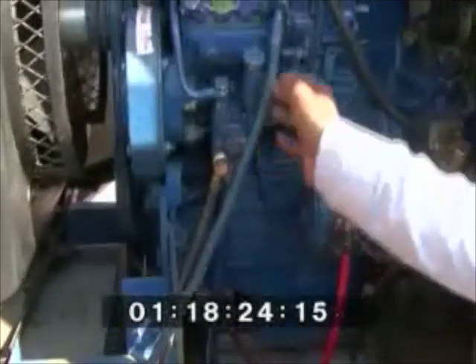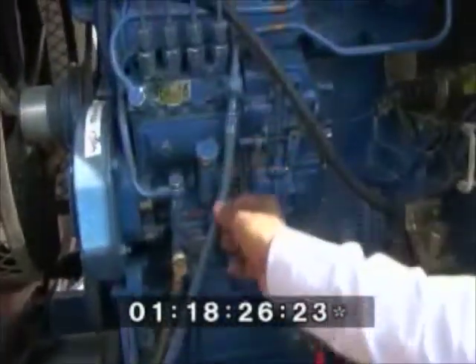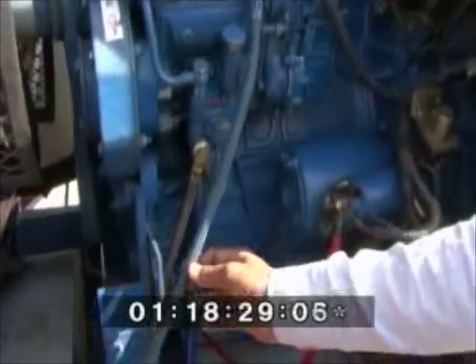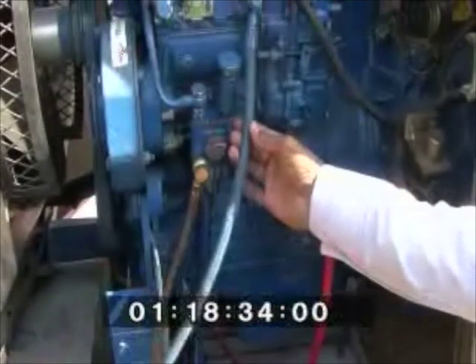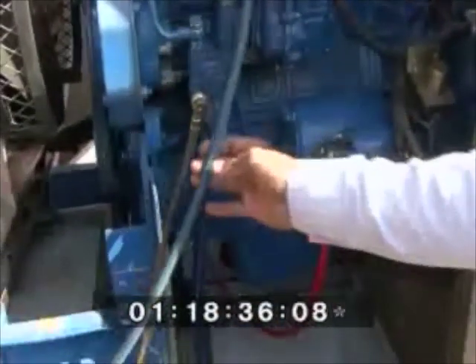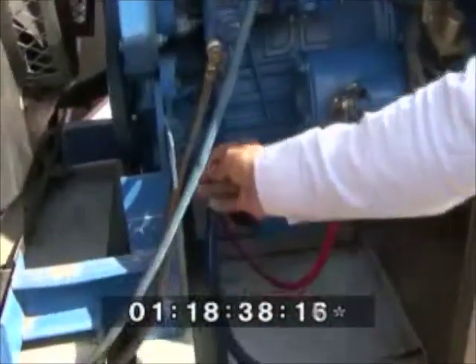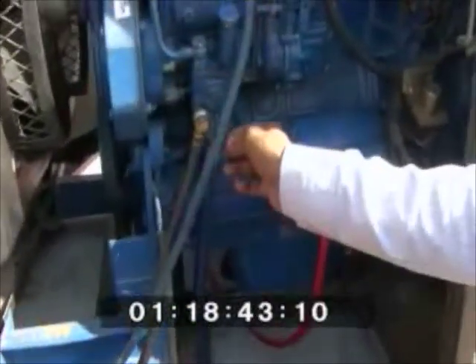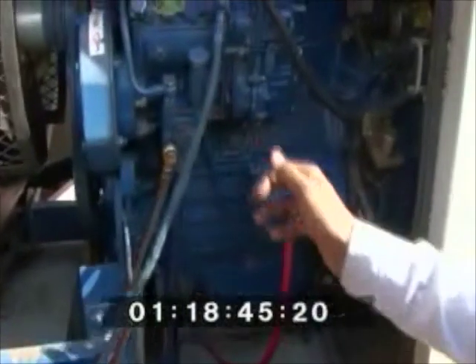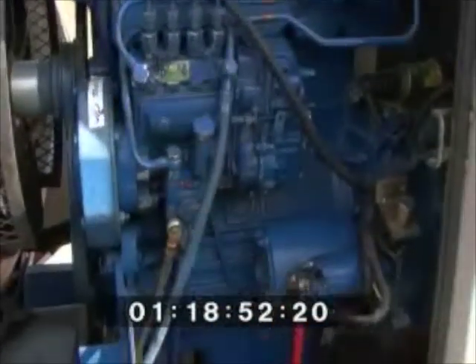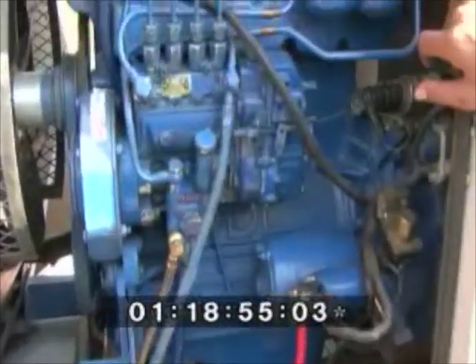We need to check the hardness of the pipe and whether there are any cracks on it. A crack will lead to diesel seepage and also might pull in air into the system, which creates problems in the DG working. So, in case the pipe becomes hard or a crack is developed, it needs to be changed.